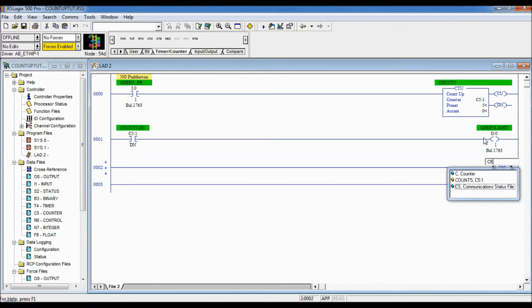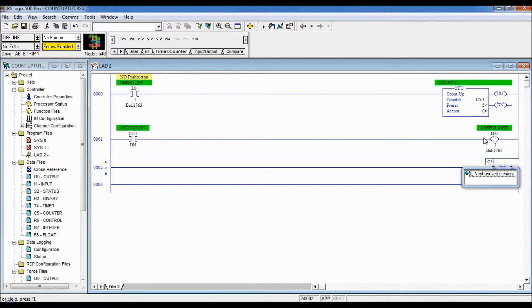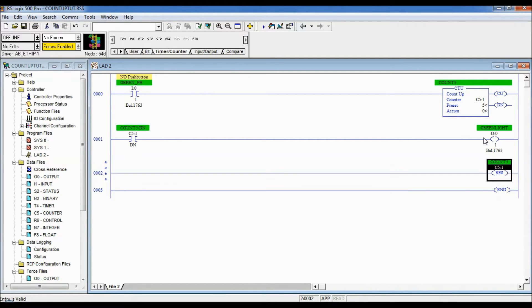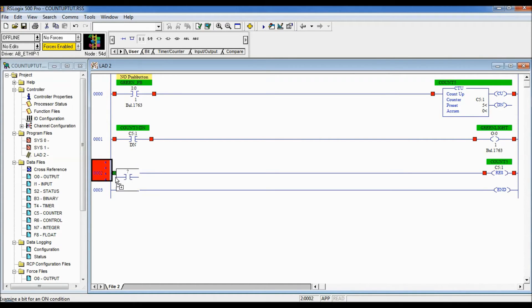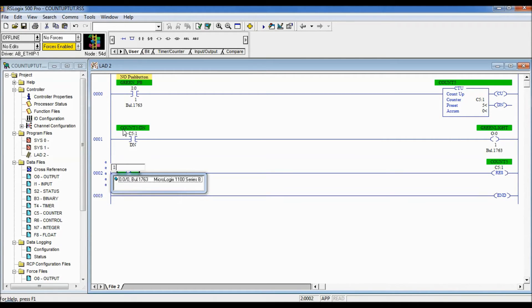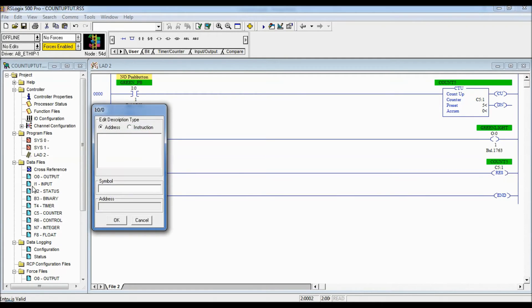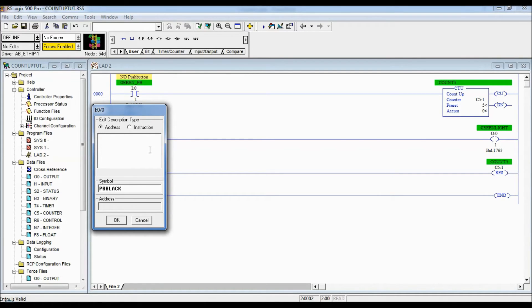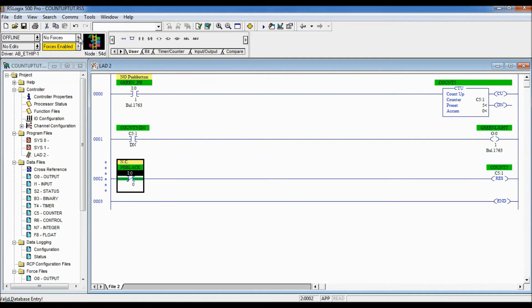And it's gonna be reset when I press the normally closed black push button. So I have to use examine if closed because it is a normally closed push button and it is located at I colon zero slash zero. I'll give it a name pb black normally closed. And we go okay. All right so let's download this in.